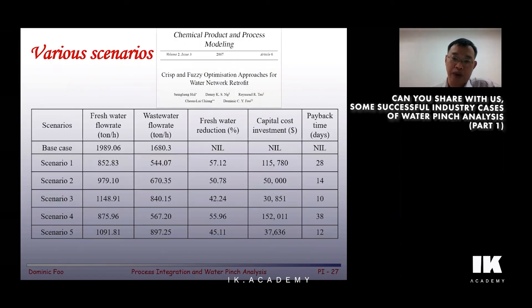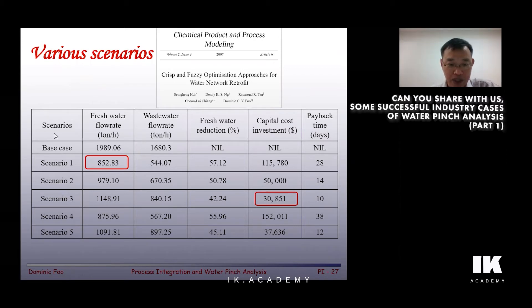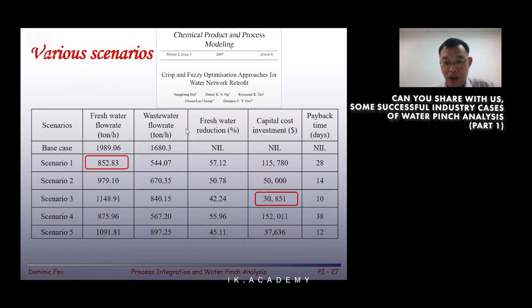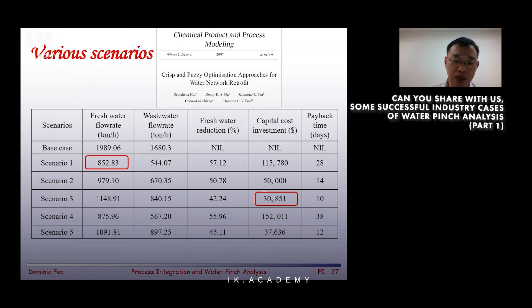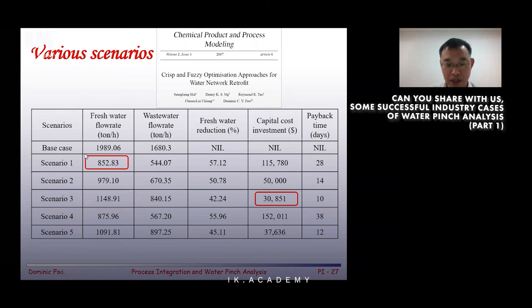So in fact, we actually moved on to do it using a different approach. The table here shows a comparison of different scenarios. We adopted a retrofit approach, meaning that rather than saving to the maximum extent — because water pinch analysis can identify the minimum water usage — we do not adopt for that. Even though it can save us the minimum fresh water, you can see Scenario 1: the result that it boxed out is 852. That is the minimum fresh water scenario.